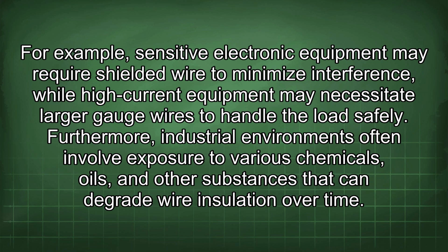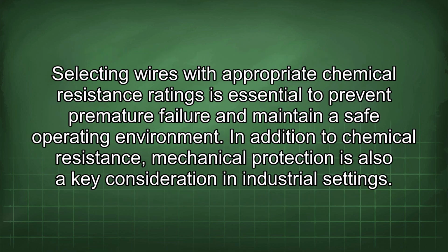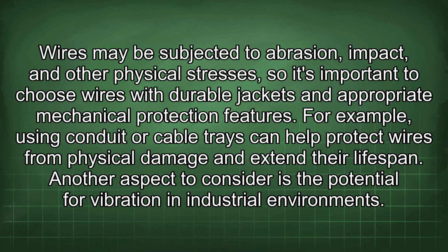Furthermore, industrial environments often involve exposure to various chemicals, oils, and other substances that can degrade wire insulation over time. Selecting wires with appropriate chemical resistance ratings is essential to prevent premature failure and maintain a safe operating environment. In addition to chemical resistance, mechanical protection is also a key consideration in industrial settings. Wires may be subjected to abrasion, impact, and other physical stresses, so it's important to choose wires with durable jackets and appropriate mechanical protection features. For example, using conduit or cable trays can help protect wires from physical damage and extend their lifespan.